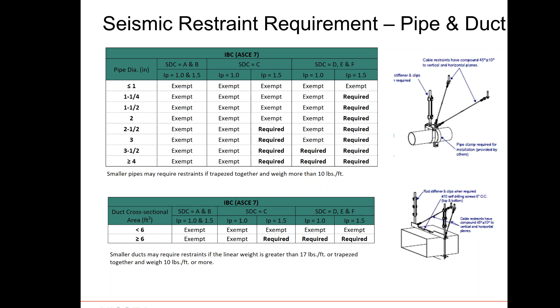So any contractors that are listening, there are some strategies obviously that can be done. You might not want to trapeze smaller pipes together to reduce your seismic scope. The same thing applies for duct, so you need to be careful with regards to double wall duct or thicker gauge ductwork that passes the weight requirement.